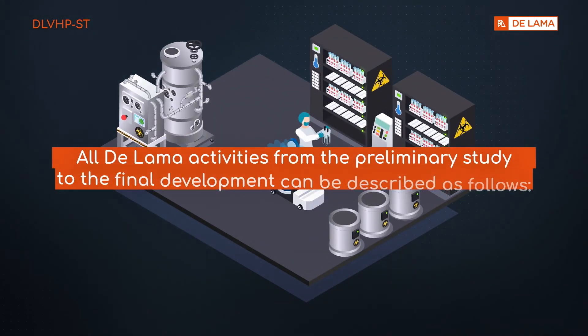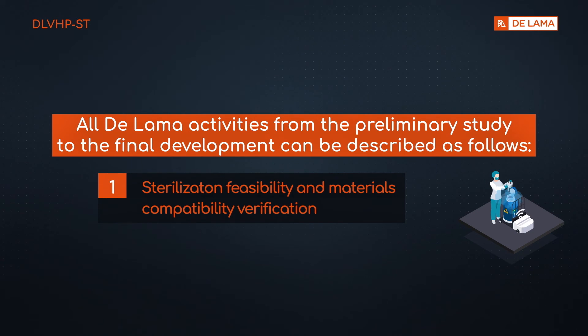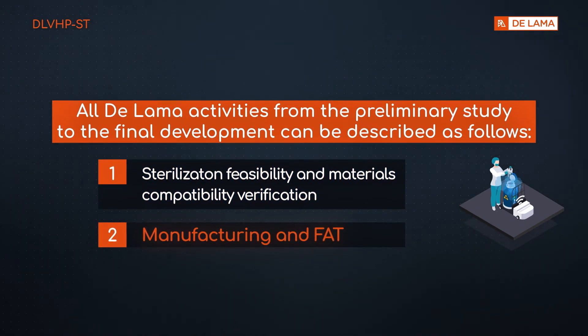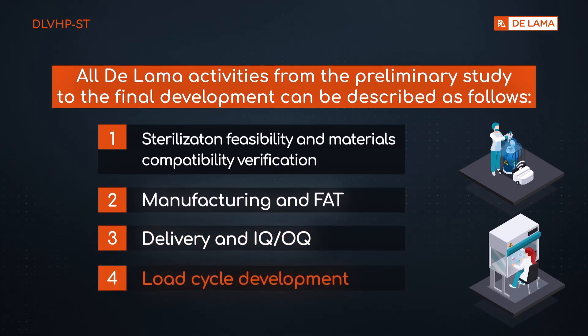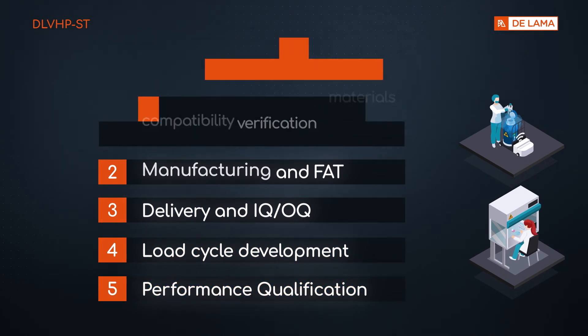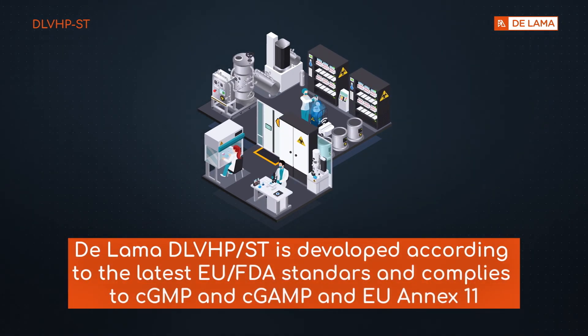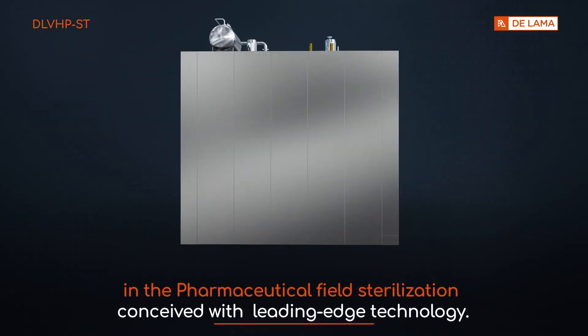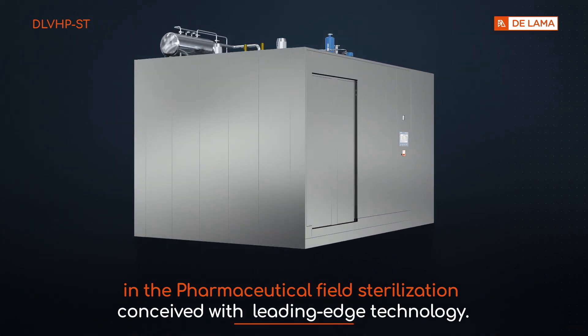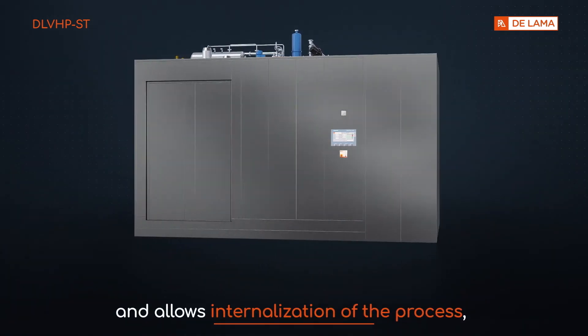All De Lama activities from preliminary study to final development include: sterilization feasibility and materials compatibility verification, manufacturing and FAT, delivery and IQ-OQ, load cycle development, and product validation. De Lama DLVHP-ST is developed according to the latest EU and FDA standards, and complies with cGMP, cGAMP, and EU Annex 11. DLVHP-ST is the outcome of 70 years of first-hand experience in pharmaceutical field sterilization, conceived with leading-edge technology. This low-temperature technology is also environmentally friendly and allows internalization of the process, achieving greater control and a cost-saving effective solution.